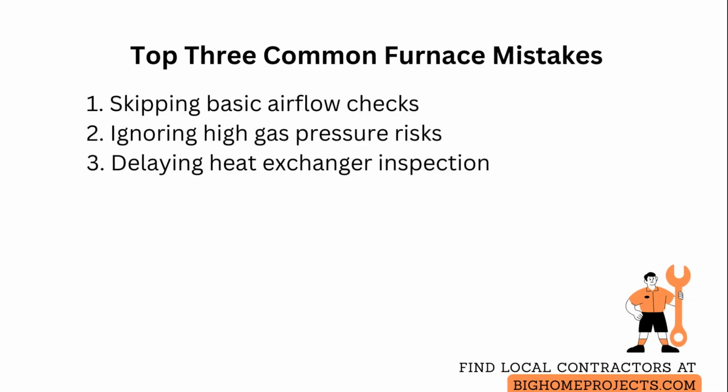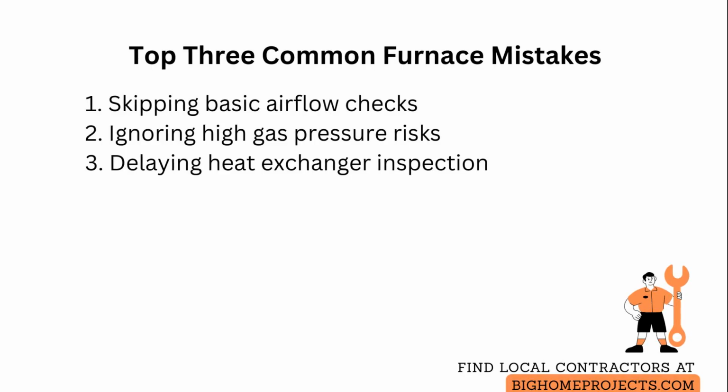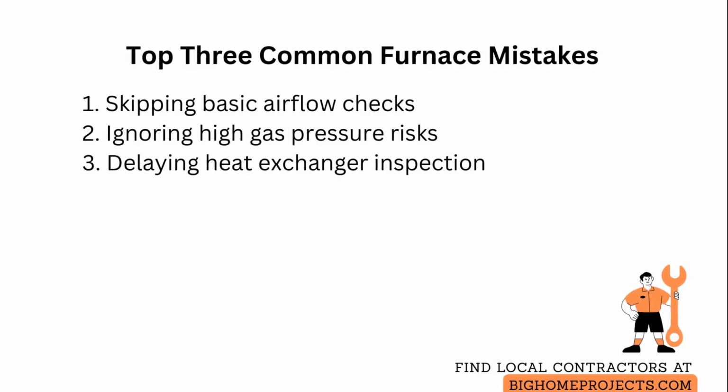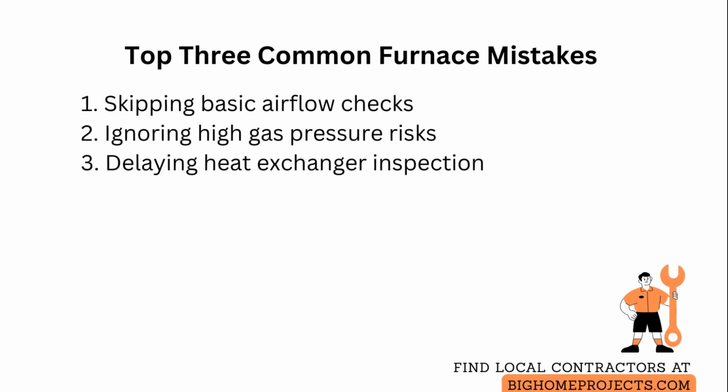Another frequent issue is assuming the furnace produces normal heat when the real problem is high gas pressure or burner misadjustment. So do not skip a pressure and combustion analysis. Correct the regulator and adjust the burner screws to manufacturer specifications.